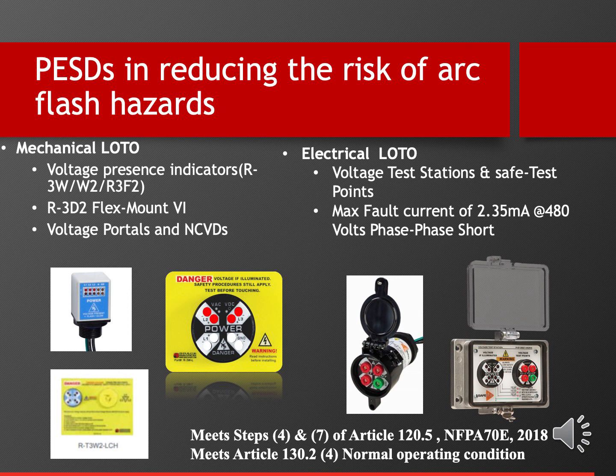Then performing an absence of voltage test inside the panel exposes the electrical worker to higher incident energy and arc flash hazards. So this is one of the most risky tasks. The voltage test station and the safe test point, which you see on the right side of the slide, allow the qualified electrical worker to perform the live-dead-live test, or what you call the 3-point test, from outside the electrical cabinet using an adequately rated meter or test instrument, which again meets step 7 of NFPA article 120.5.